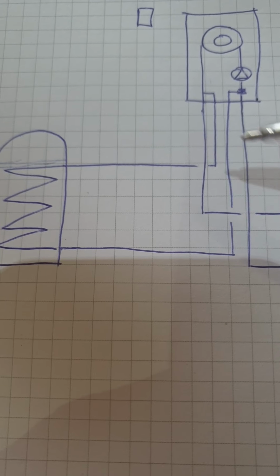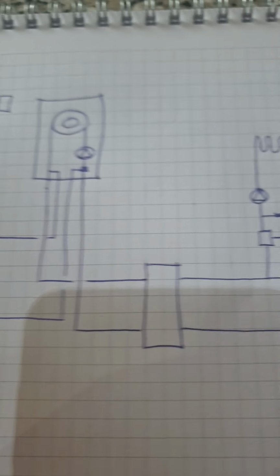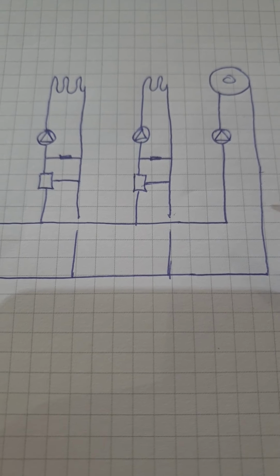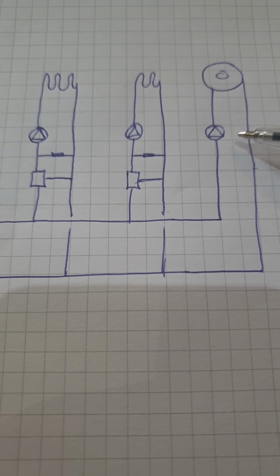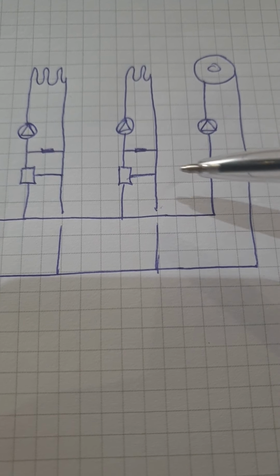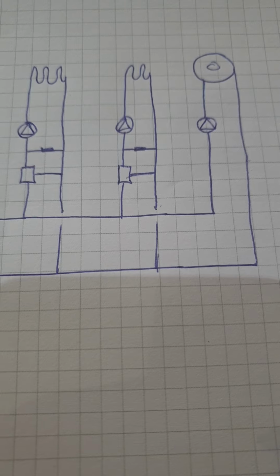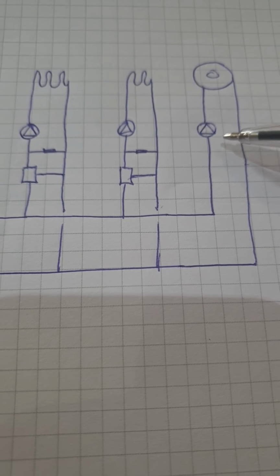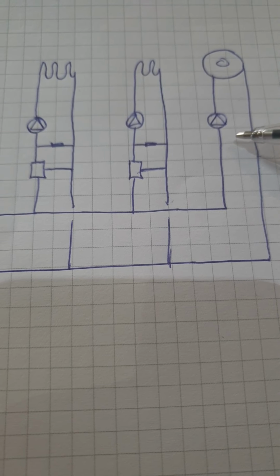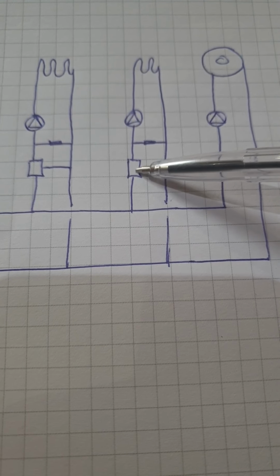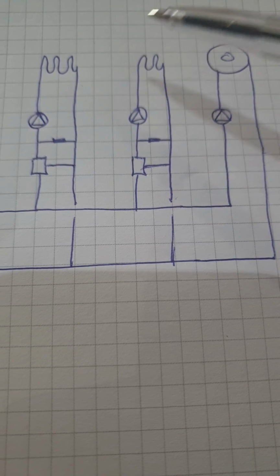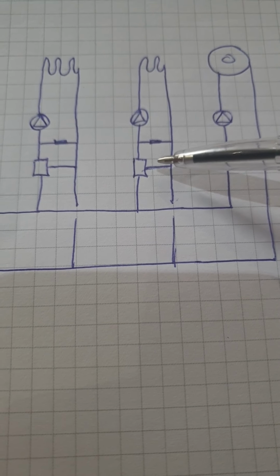Okay. So once hot water is heated, it will then look for demand down the system. Now the Viessmann 200 can run multiple circuits. I think as standard from the box it can run 2 mixed and 1 unmixed circuit, and you have to add an additional control if you want to go beyond the standard 3 circuits. So for my designs, normally the unmixed circuit will be the highest temperature circuit, and this allows the motorized blending valves to reduce the temperature in the other floors or other zones.